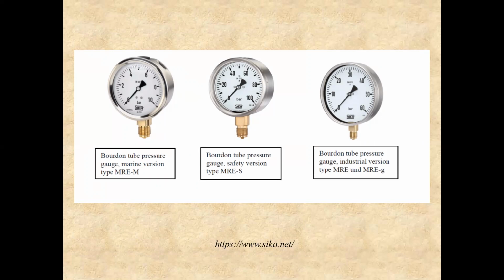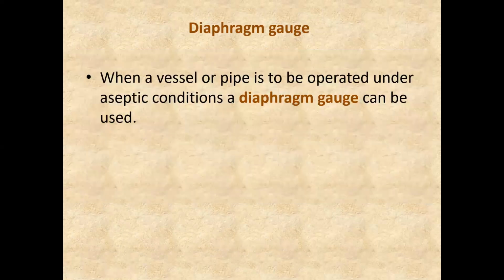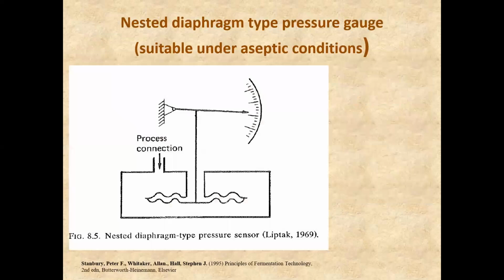After the Bourdon tube pressure gauge, let's study the next type of sensor which is used to monitor the pressure. This is the diaphragm gauge. Now, when a vessel or a pipe is to be operated under aseptic conditions and you want to monitor the pressure, you can go for a diaphragm gauge. And this is the picture of a nested type diaphragm pressure gauge. It's suitable under aseptic conditions, and the principle is very simple.